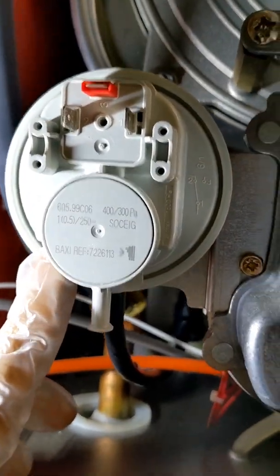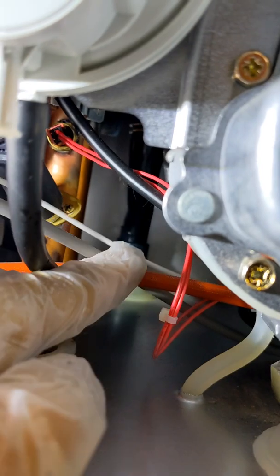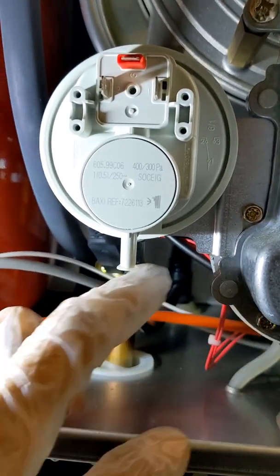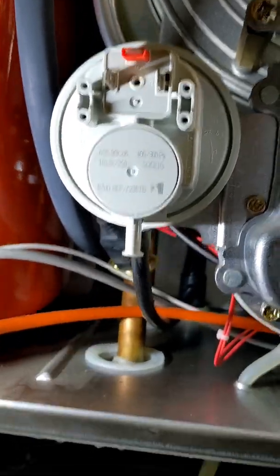Now this air pressure switch, if you look at this hose, goes back onto the condensate trap. So I'm suspecting possibly a blocked condensate, which is stopping this from giving us continuity.